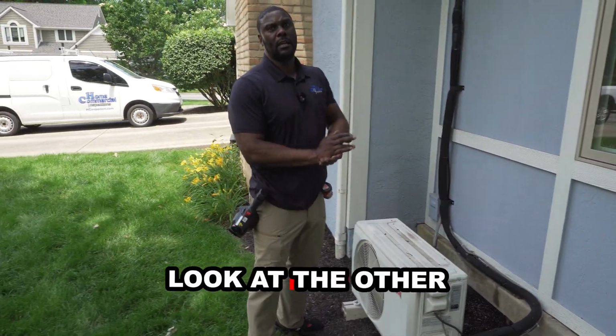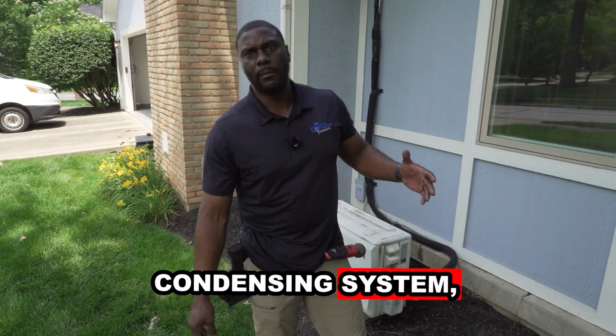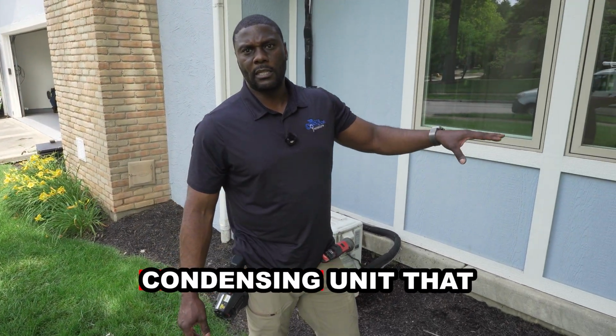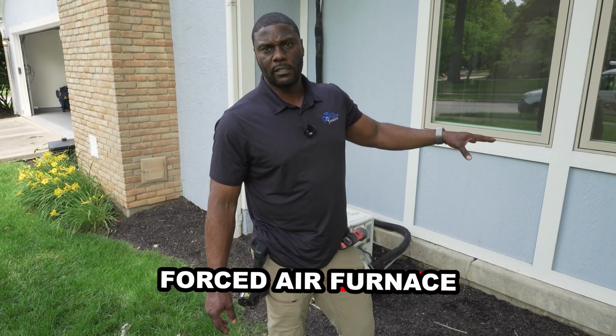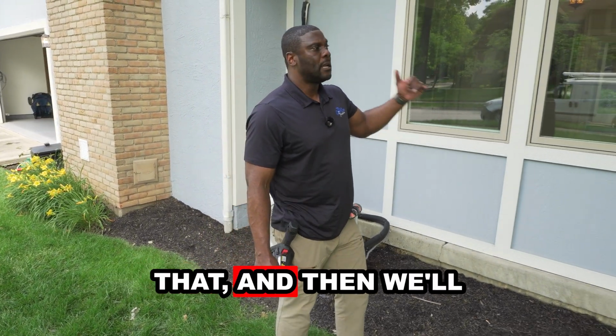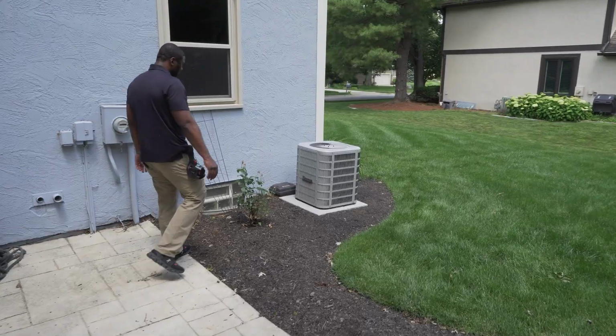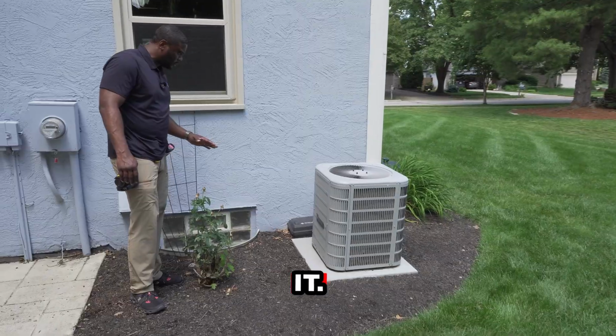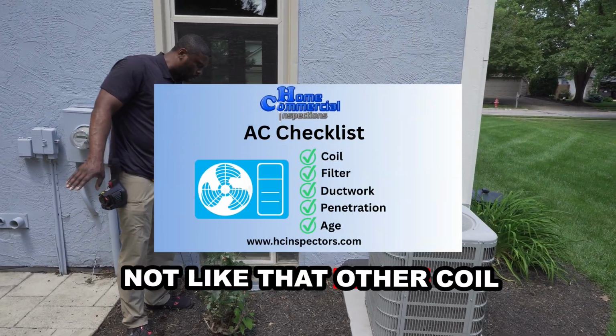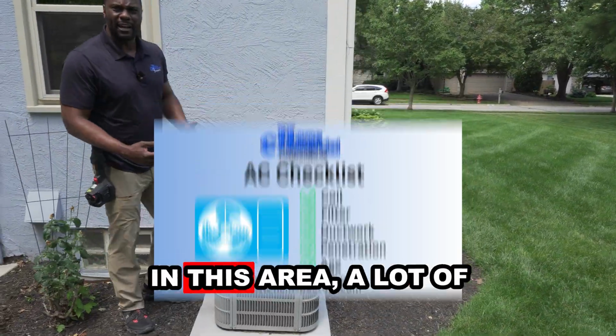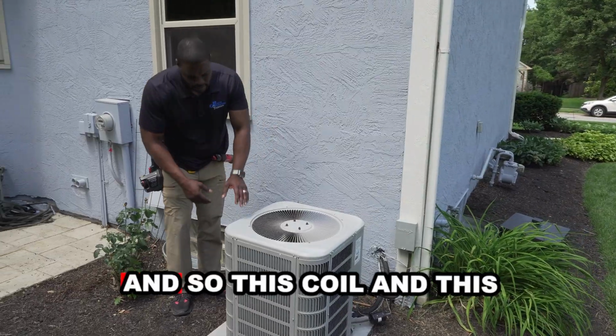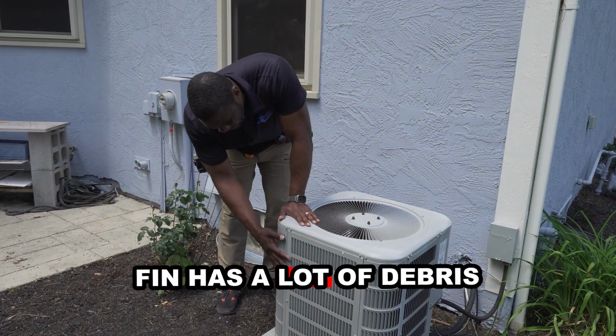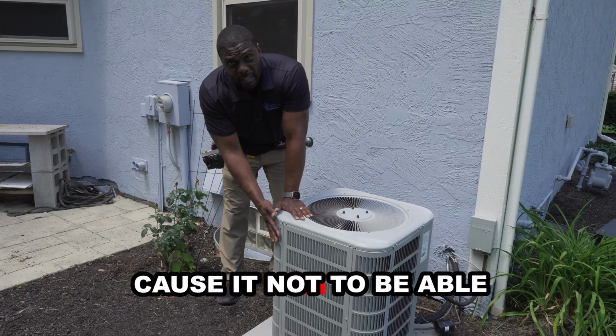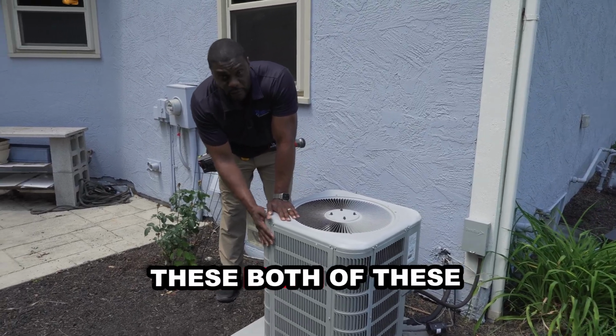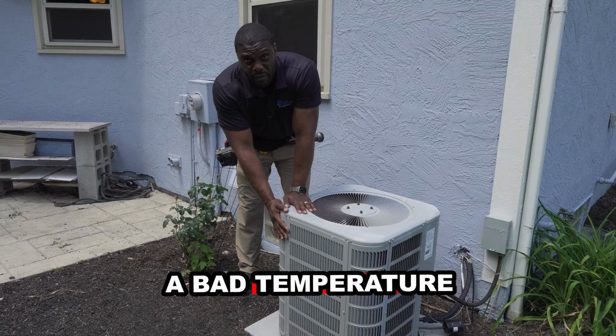So let's take a look at the other portion of the condensing system, the AC that's around the corner, the condensing unit that goes with the gas forced air furnace that's in the basement. And we'll take a look at that and then we'll head inside. So I'm inspecting the coil when I walk up to it. I want to make sure it's not like that other coil where it's covered, and it does have some of that covering. There's a lot of pollen in this area, a lot of trees dumping things. And so this coil and this fin has a lot of debris on it. So that's going to cause it not to be able to condense like the other unit. I believe both of these units are probably going to have a bad temperature differential.